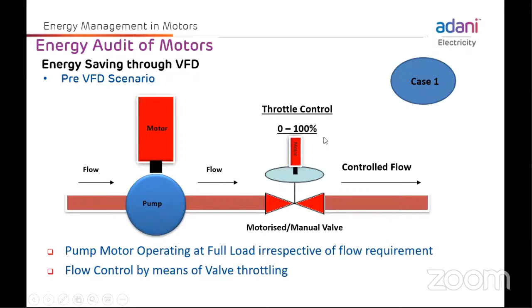You can take a simple example, one CP VFD, which maybe someone explained to you. That is a 600 kilowatt motor. Now normal consumption is 600 energy consumption, reduced to 450 kilowatt, so this is a 150 kilowatt saving.